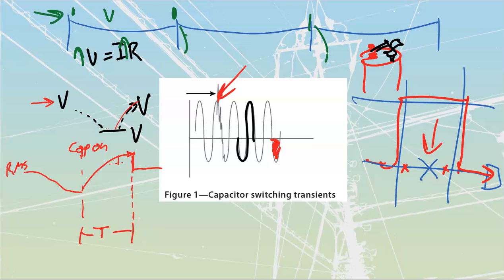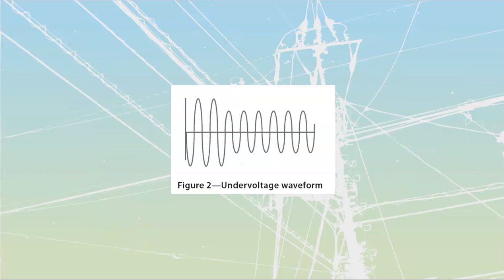If you go past that, you're dealing with undervoltage, commonly known as brownouts. Brownouts can sometimes happen as a short-term event rather than long-term—for example, if a motor starts up at one facility, especially a massive couple-hundred-horsepower motor, it can brown out the whole grid in that area until the motor comes up to speed, due to the inrush current.